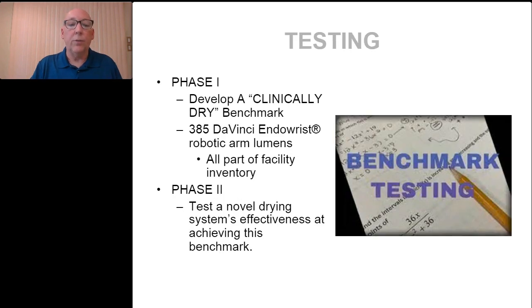The study itself had two phases. Phase one was to basically develop a clinical dry benchmark. There were 385 Da Vinci EndoWrist devices tested, all part of this facility's inventory, and testing a novel drying system's effectiveness was phase two to achieve its benchmark. So basically what happened was that all the devices were weighed, their dry weight, which was then measured against the manufacturer's specifications in the instructions for use, to determine the dry weight of each of the 385 EndoWrists that are part of this facility's inventory.